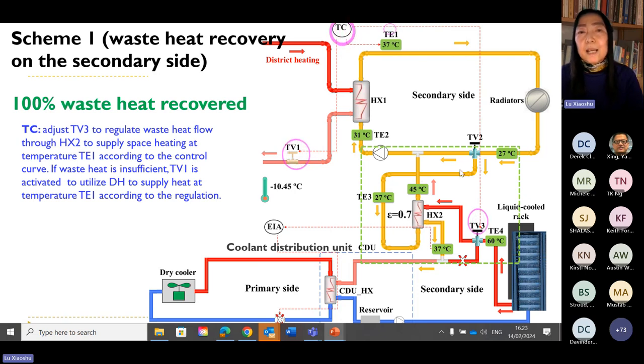The whole system control can be realized by two processes. First is TC. This TC regulates waste heat flow on the secondary side through heat exchanger HX2 to supply the temperature TE1 according to the Finnish regulation. If the waste heat is not enough, then this TC will activate TV1 that utilizes district heating or some other heat source to supply the temperature at TE1 according to the Finnish regulation. So this process can be viewed as an autonomous or independent waste heat reuse loop.